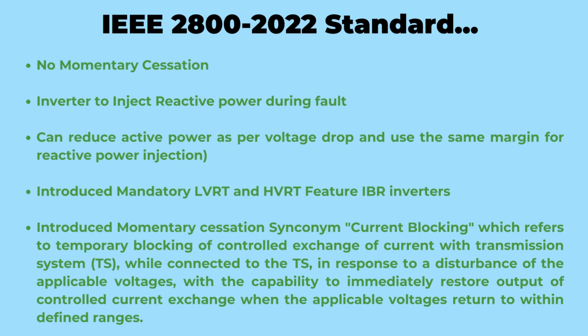In an exciting development, the IEEE 2800 standard introduces the mandatory inclusion of low voltage ride-through, LVRT, and high voltage ride-through, HVRT, features in IBR inverters. This empowers these resources to withstand voltage variations and disturbances, maintaining a stable operation throughout. To add to the intrigue, the standard introduces a synonym for momentary cessation, current blocking. This term refers to the temporary blocking of controlled current exchange with the transmission system, TS, when applicable voltages experience a disturbance. However, the IBR retains the capability to swiftly restore the output of controlled current exchange once the applicable voltages return to within defined ranges.